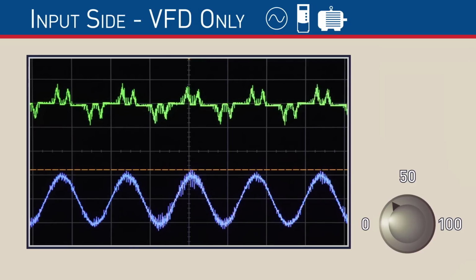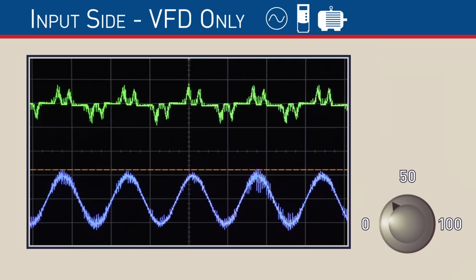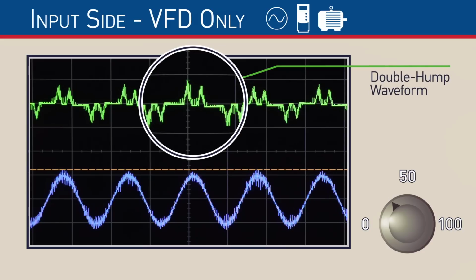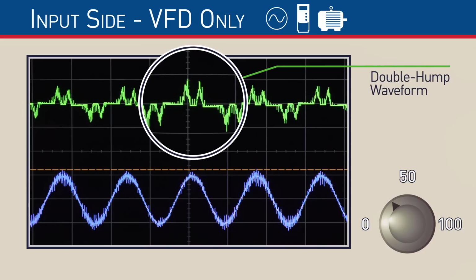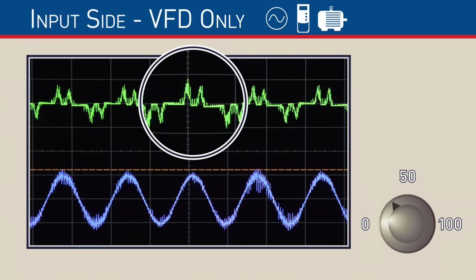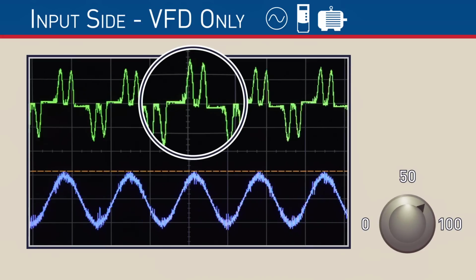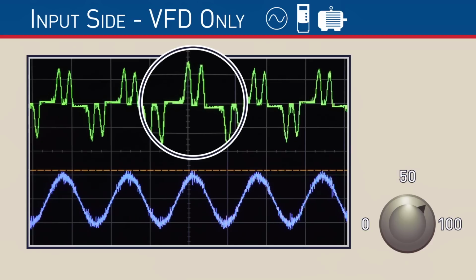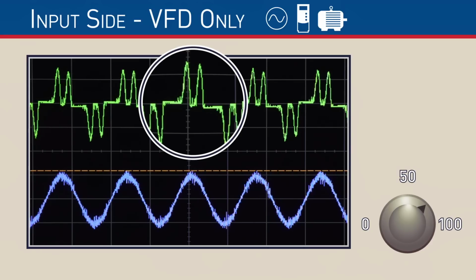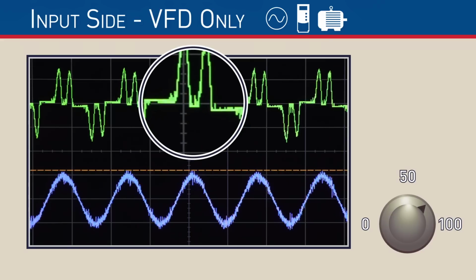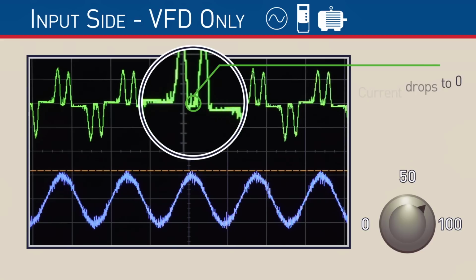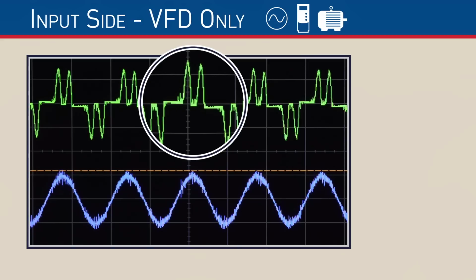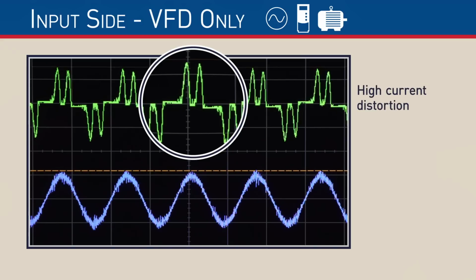We see right away that the current waveform has been impacted. It is no longer a sine wave, but instead takes on a double hump form that is characteristic of VFDs. This is an indication of harmonics on the system. As we add to the load, the double hump waveform increases in magnitude, as does the level of harmonics. Looking closely, we can see that between the humps, the current drops to zero, and the top of the humps grow taller. This is an indication that our current distortion is high.